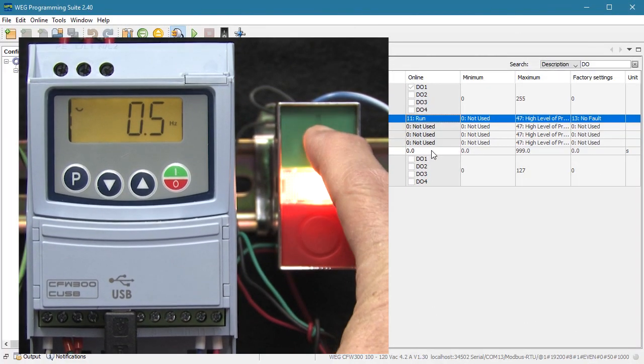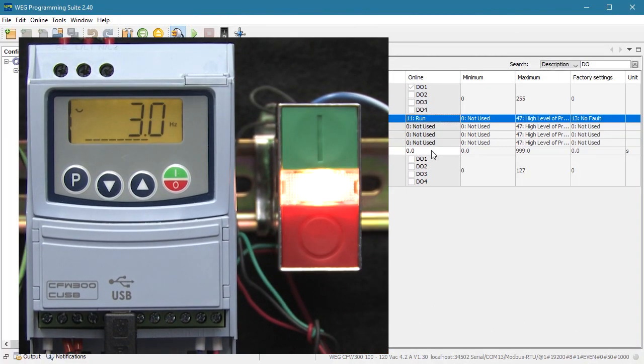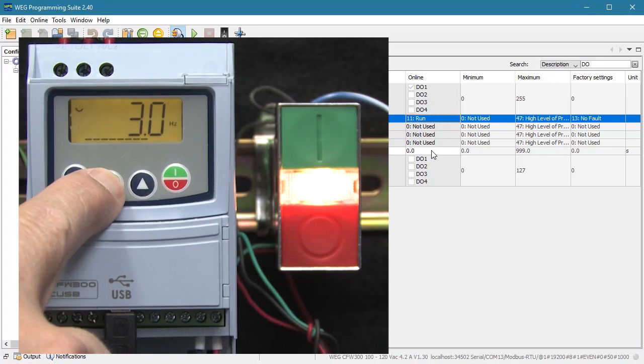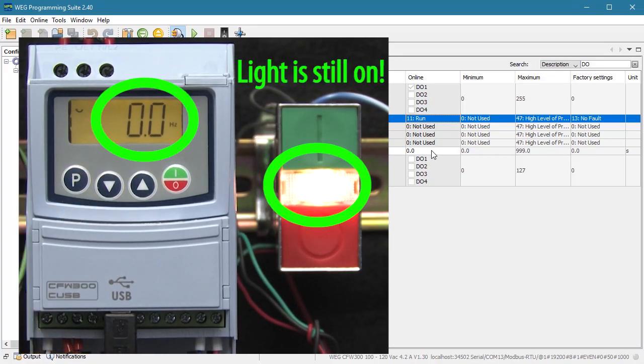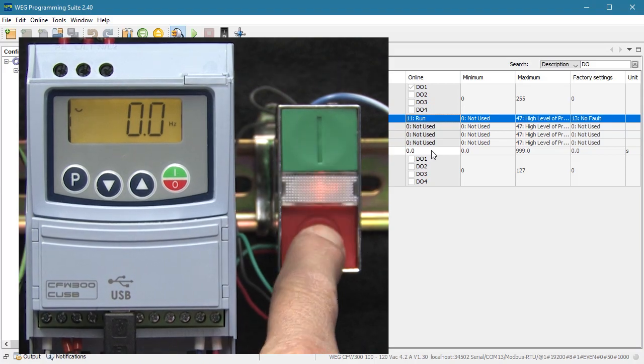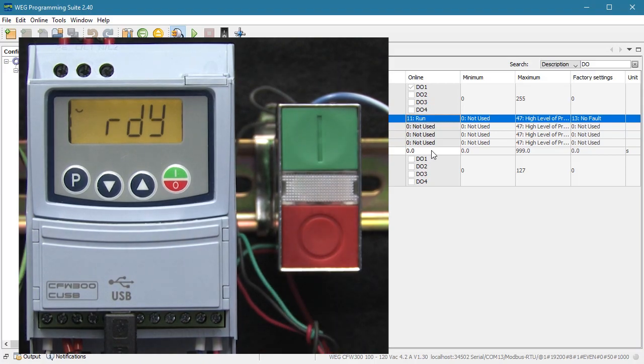Now one side note. The light stays on as long as the run command is active – even at zero speed. That way you know the drive has actually been stopped or if the drive is running but at zero speed.